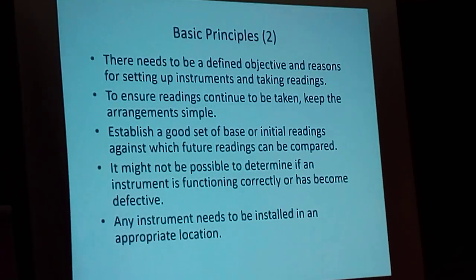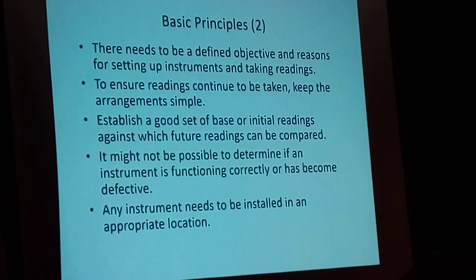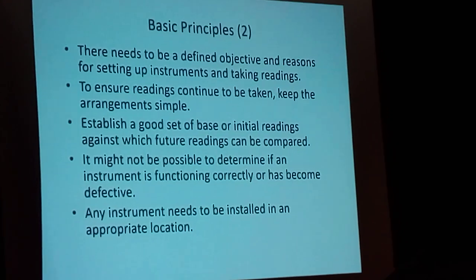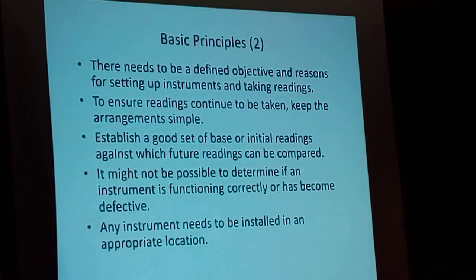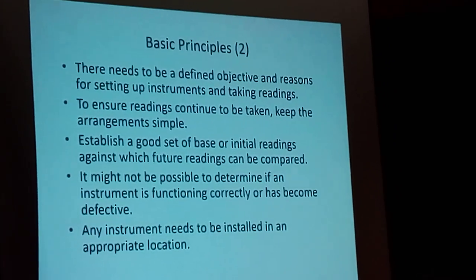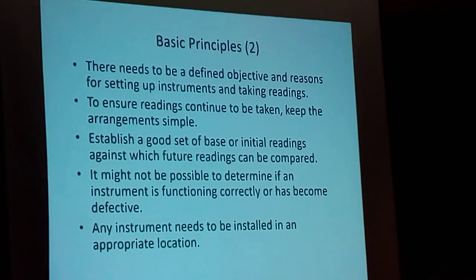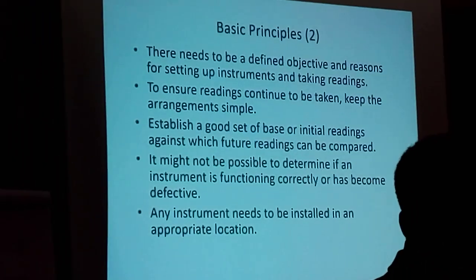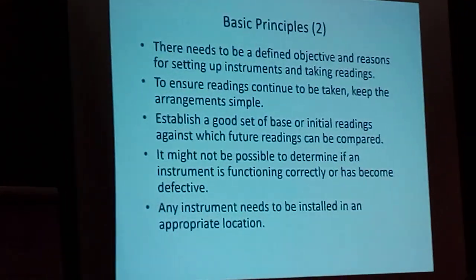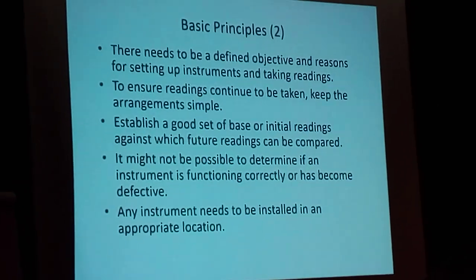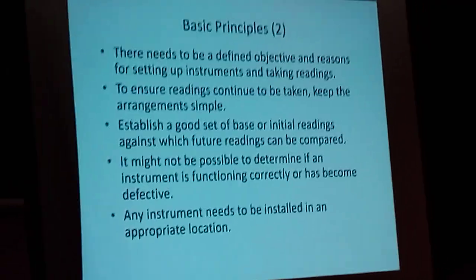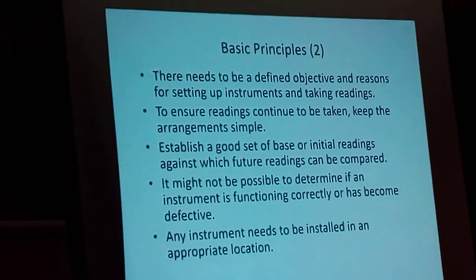There needs to be a defined objective and reasons for setting up instruments and taking readings. To ensure readings continue to be taken, keep the arrangements very simple. Establish a good set of base or initial readings against which future readings can be compared — that is very important. Sometimes the designers will need to help you with this. It might not always be possible to determine if an instrument is functioning correctly or has become defective, so any instrument needs to be installed in a perfect location.